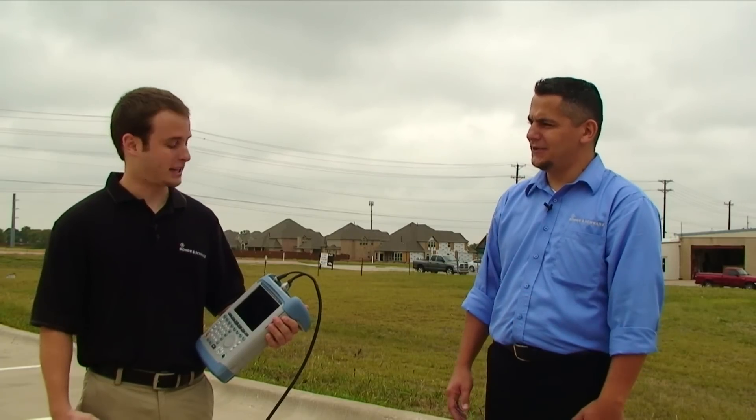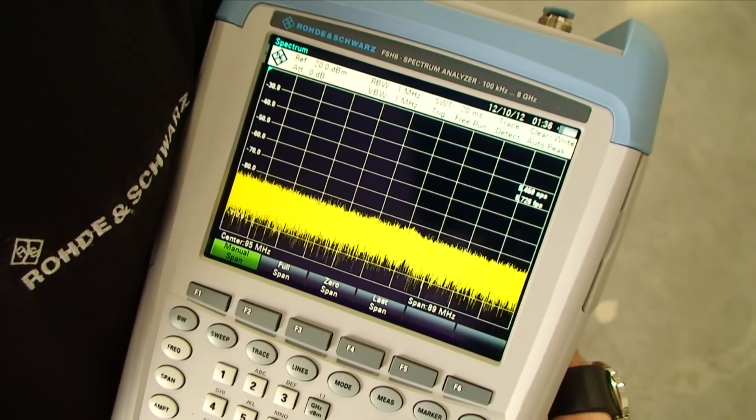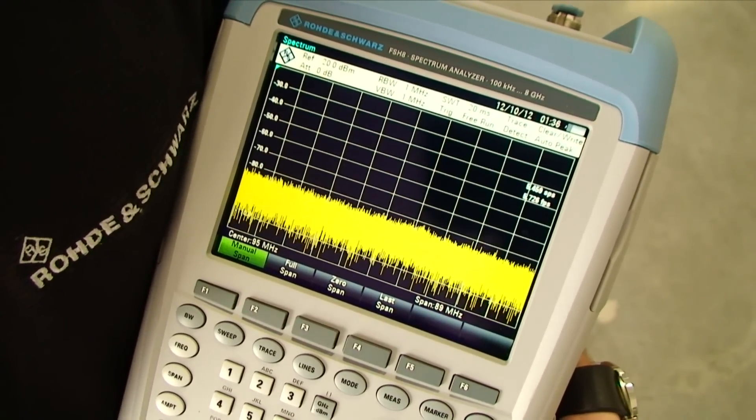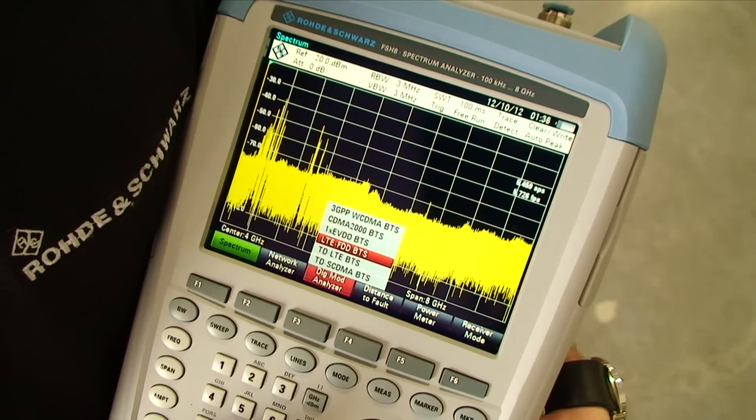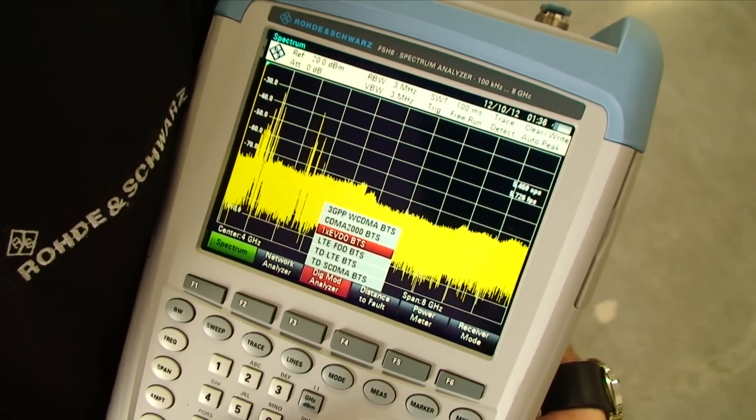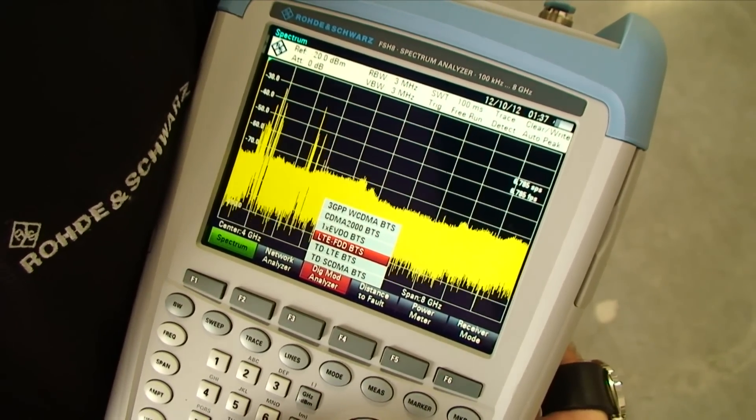Could you walk us through the settings? Absolutely, I can show you a few things. The first thing I'm going to do is preset the instrument to wipe out the settings. I'm going to switch over to the digital modulation analyzer mode of the FSH. As you can see, we support different technologies such as CDMA, EVDO. In this case, I'm going to select LTE FDD.